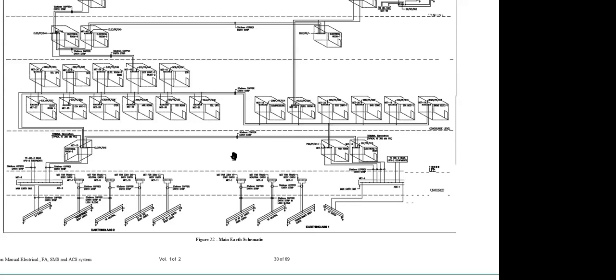What I was saying at the start: as you see from here, each and every equipment is earthed with two earth strips. This is mandatory. Why is it mandatory? It is very simple. Due to some reason, if one earth fails, then the other should be in operation. In that case, there will generally be no situation where the equipment is not getting any earth. That is the whole reason we are providing two earth strips. If we provide one earth strip, and in case there is a breakage or due to any reason that particular earth bus is not working, then the equipment is at risk because it is not getting any earth.